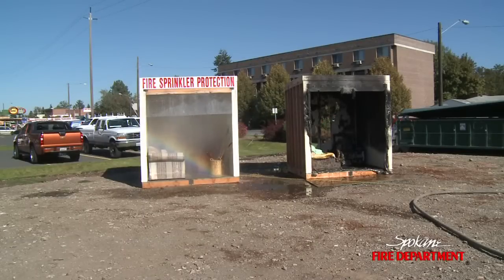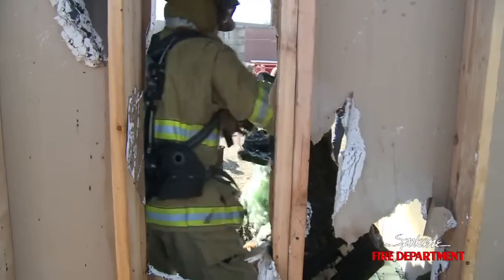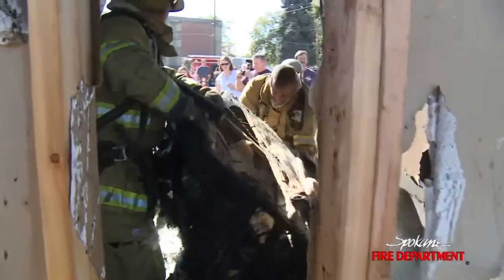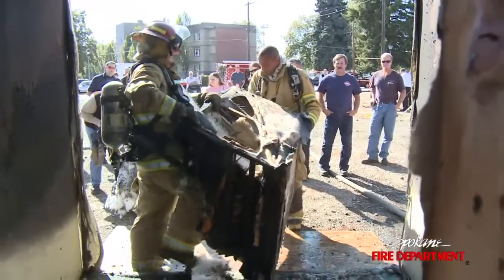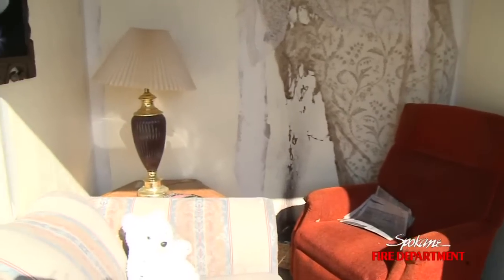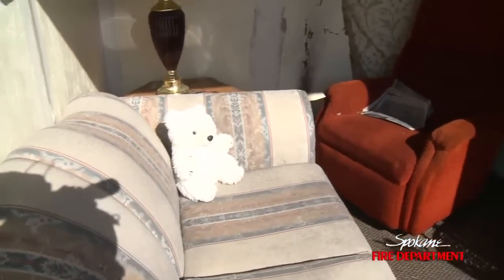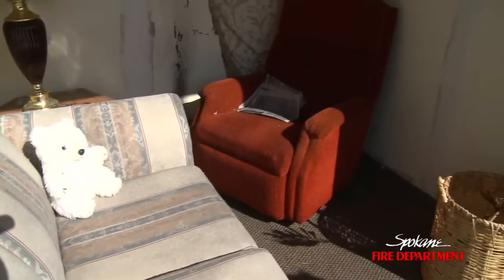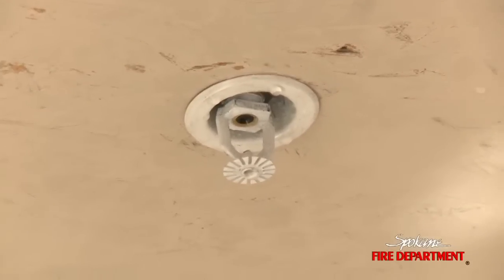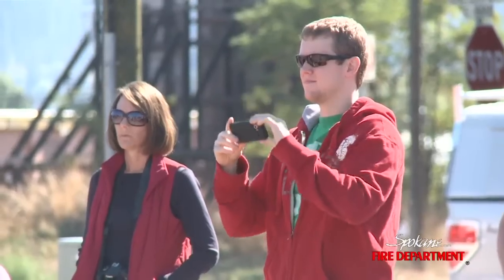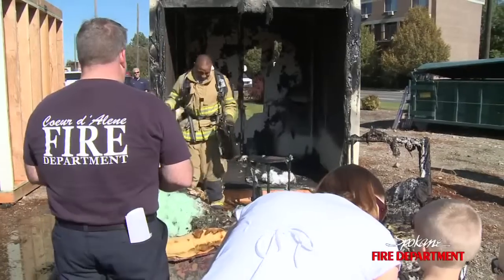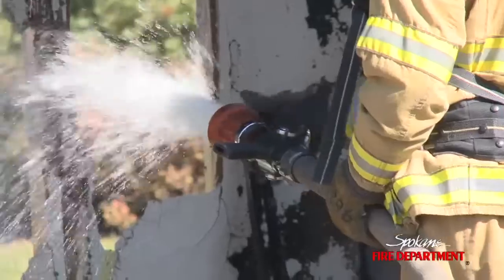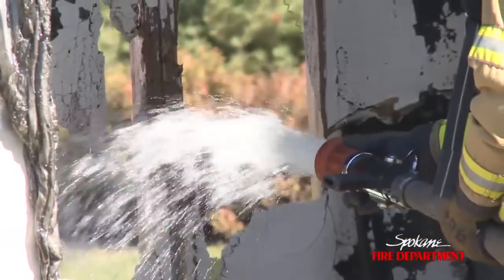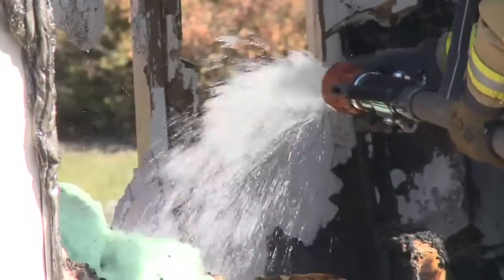If you look at the damage to the room on the right and how long it would take to recover that room, versus the damage on the left and how long it would take to recover that room, you see a significant difference. You don't see nearly the smoke damage, virtually no smoke or heat damage in the fire sprinkler protected area. Certainly you have some water damage, but again, that water damage is minimal compared to what it would be if a firefighter was operating a hose line at 150 to 200 gallons per minute for any length of time.